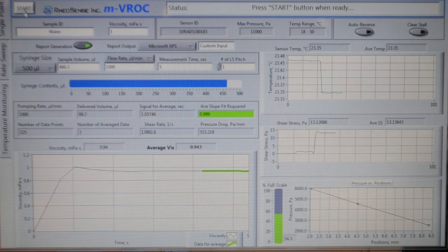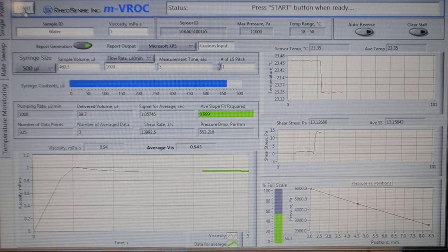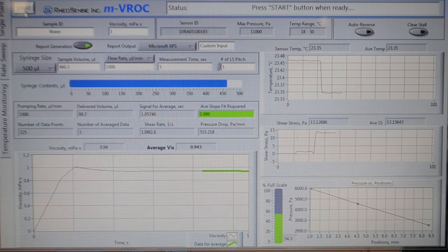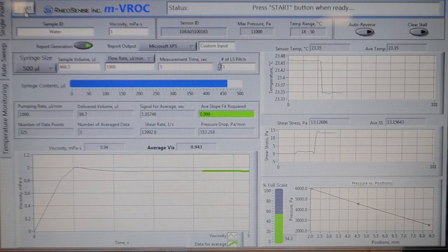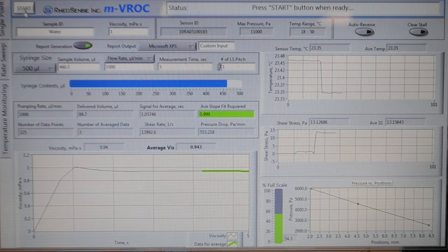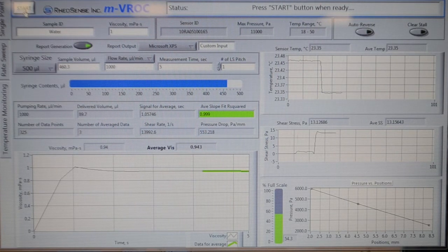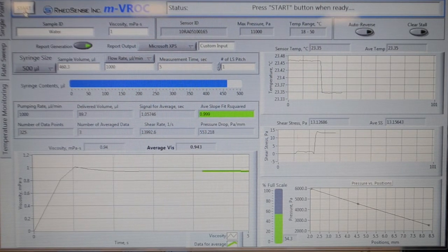After your sacrificial run, you may move on to step 4, single point measurement. To obtain a single point measurement, repeat what you did for the sacrificial run, except save the data this time.